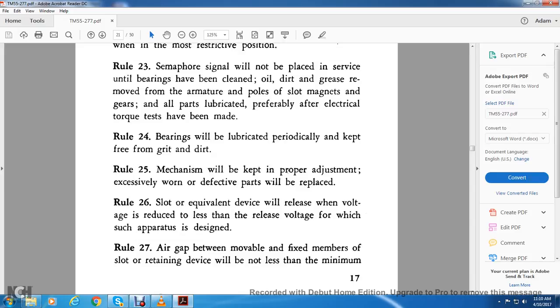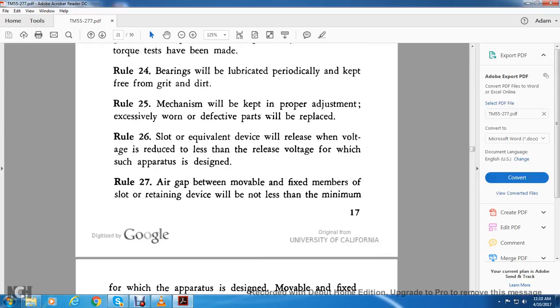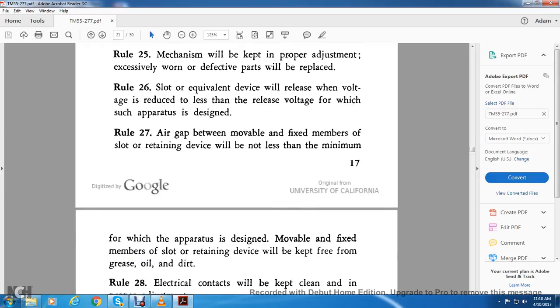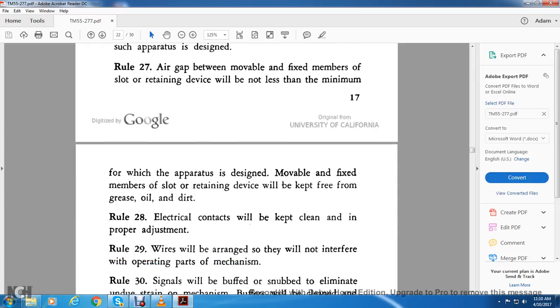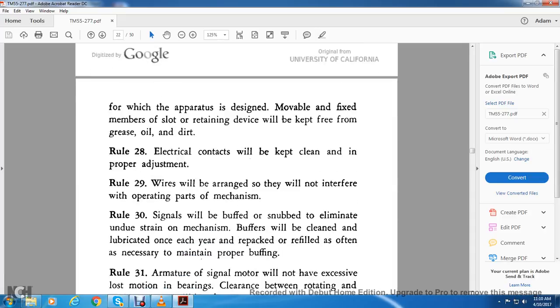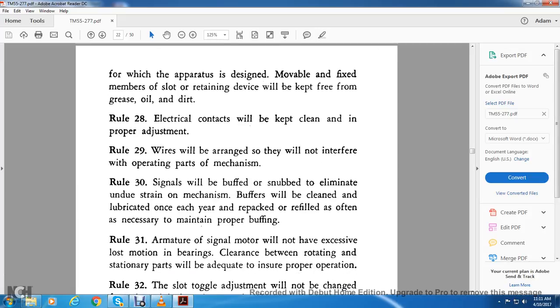Rule 27. An air gap between the movable and fixed members of the slot retaining device will not be less than the minimum for which the apparatus is designed. Movable and fixed members of slot retaining devices will be kept free of grease, oil and dirt. Rule 28. Electrical contacts will be kept clean and in proper adjustment. Rule 29. Wires will be arranged so that they will not interfere with operating parts of the mechanism.